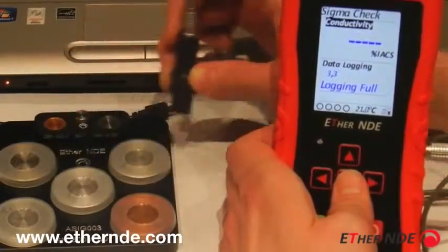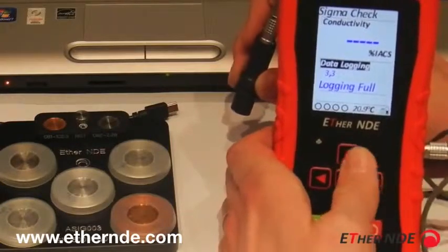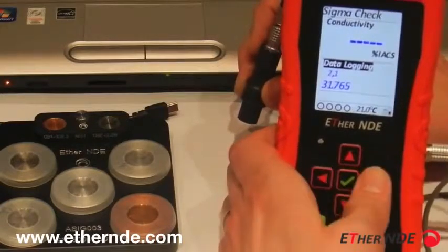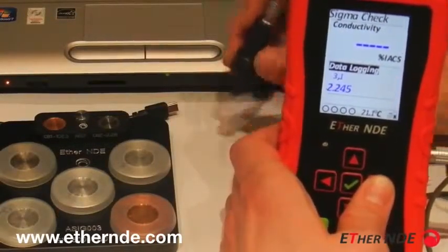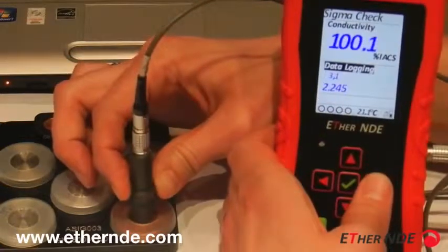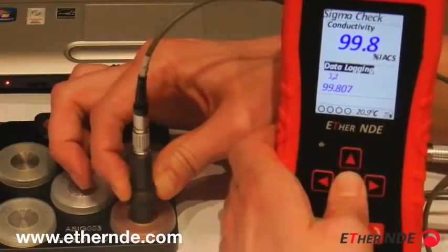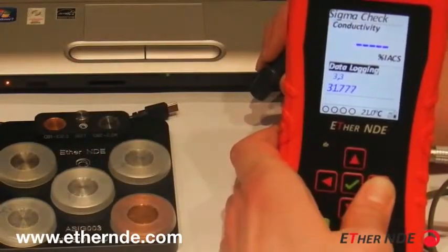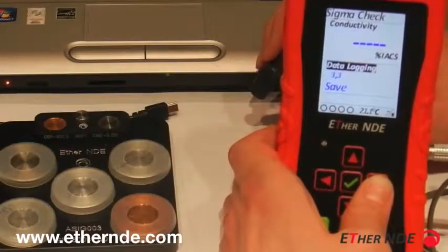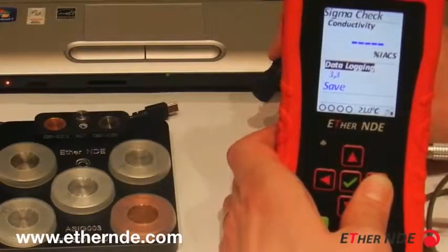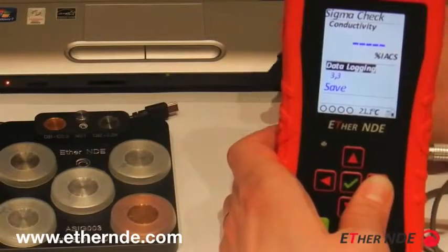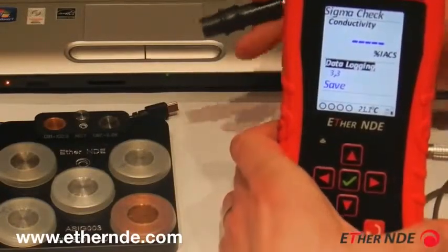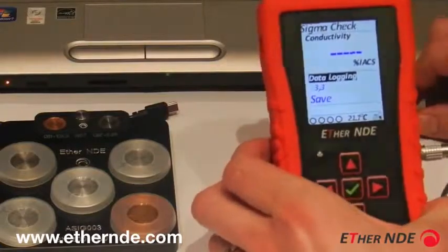Now again, the advantage of storing it to RAM, if I now go down to the data logging pane, I can then go left and scroll through all previous values. If any of these look suspect, then I can take another reading, and then pressing the tick, it'll overwrite the previous reading. If I go back to the last reading, and then go right again, I have the option to save. So now I can save that data to the memory card for future analysis and continue with a separate or a new data logging session. But what I should do now is analyse the data on a PC.